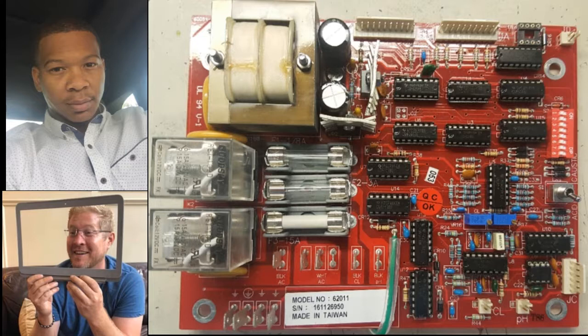Okay. So you still could have a bad fuse. When the controller says, "I want to feed sanitizer," that relay is going to close even if the fuse is tripped, but they wouldn't get power to the pump because the fuse is blown. Correct. Very good. And that would be a good indication for them: if the light's coming on and the relay is clicking, but they're not getting any power, they could go right to the fuse. Right to the fuse.